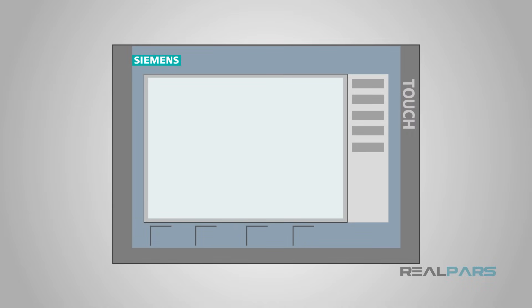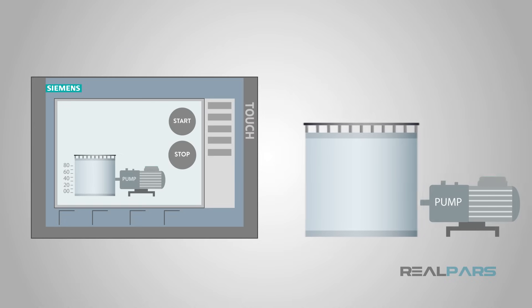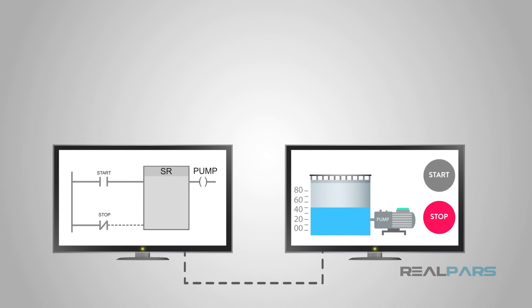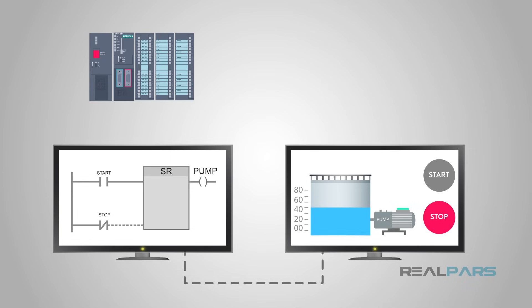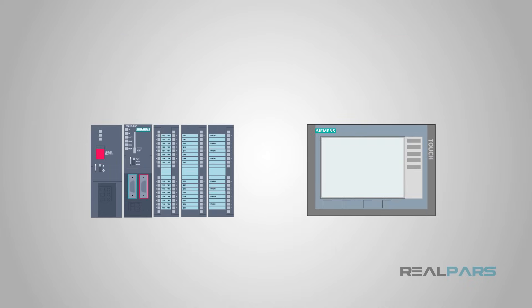For example, an HMI may have a large tank displayed on the screen with the level of a liquid displayed. Next to the tank is a pump to lower the liquid level. An HMI can also have the start and stop button displayed and usable on the screen next to the pump. This display would be able to actually turn the pump on and off. But it's not as easy as just placing a button or a tank on the screen — the person programming the HMI has to program each indicator and button to a specific input or output address of a PLC.